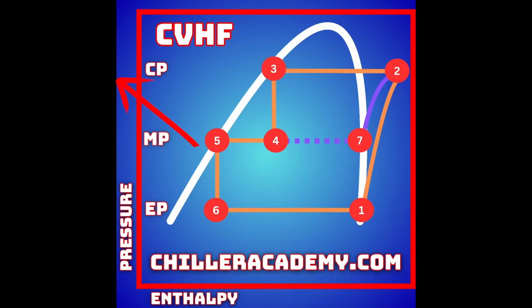So this is my pressure on the chart. This is the actual enthalpy. Remember, enthalpy is just referencing heat content. So the further to the left we are on this chart, the more room we have to take in heat. And the further to the right we are, the less room we have to take in heat. That is the basic fundamental, and the higher we are on this chart, the higher the pressure. The lower we are, the lower the pressure.